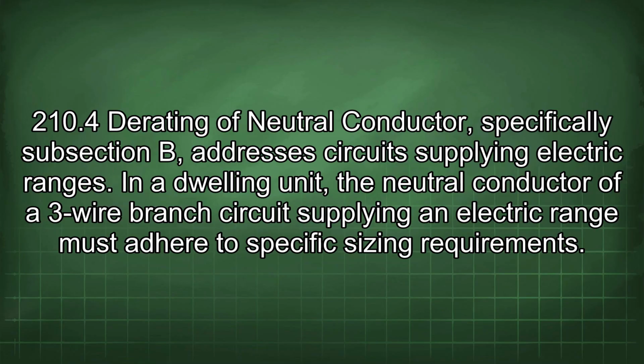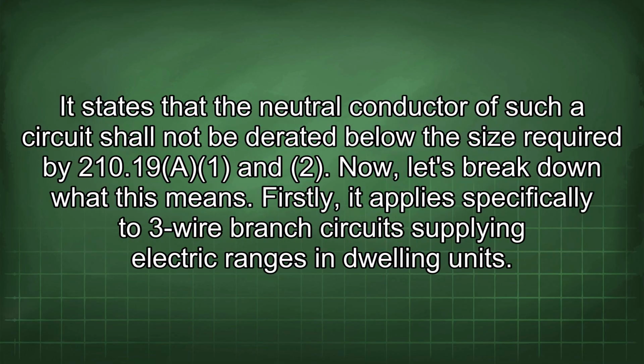210.4 Derating of neutral conductor, specifically subsection B, addresses circuits supplying electric ranges. In a dwelling unit, the neutral conductor of a 3-wire branch circuit supplying an electric range must adhere to specific sizing requirements. It states that the neutral conductor of such a circuit shall not be derated below the size required by 210.19 A. Now let's break down what this means.